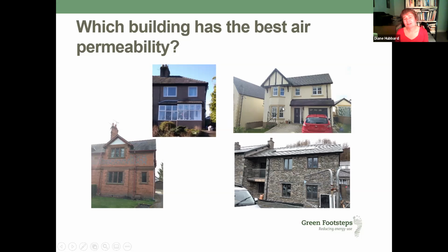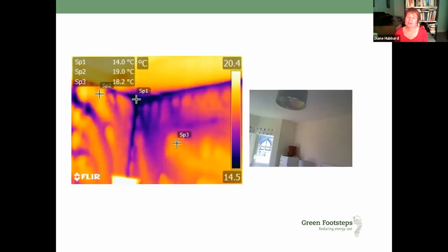I'd like to look a little bit more at the situation with this new build house. This is an image I took inside the property. Though it's not showing air leakage into the building, those fingers of cold air we were looking at before, it's a really good illustration of one of the problems that we have, both with new builds and also when we retrofit properties.